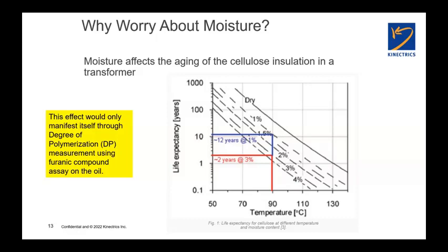And as mentioned, when we're talking about life expectancy of transformers, it really boils down to the life expectancy of the paper. Anything on a power transformer, almost anything, you can replace while the transformer's in the field. If you've got gauges that are no good, you replace the gauges. If the radiators start to rust, you can replace the radiator. Even the oil, as part of the insulation system, if the oil's gone bad, you can take the oil out, pump it out, and you can regenerate it or replace it with new oil.